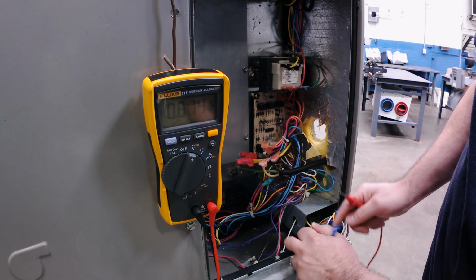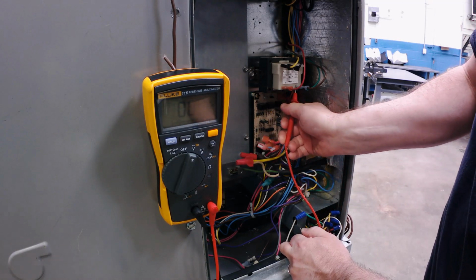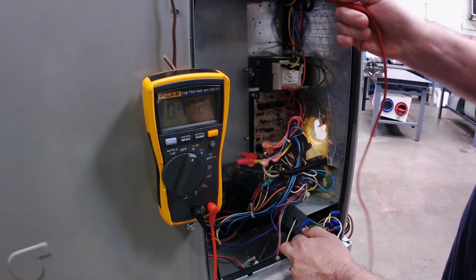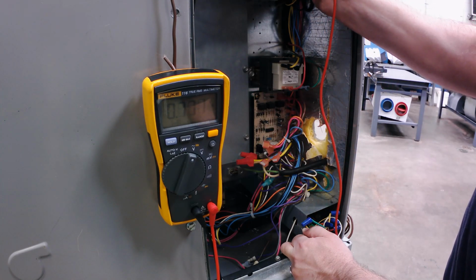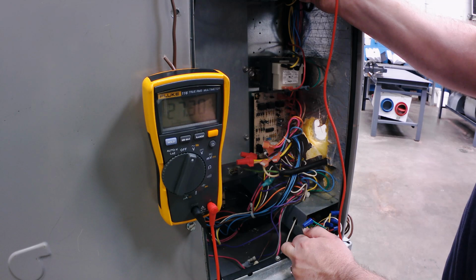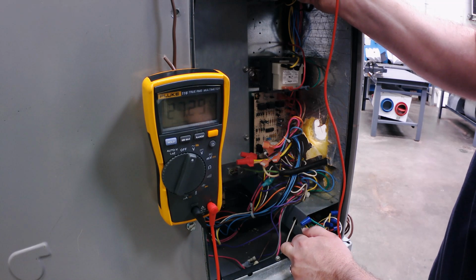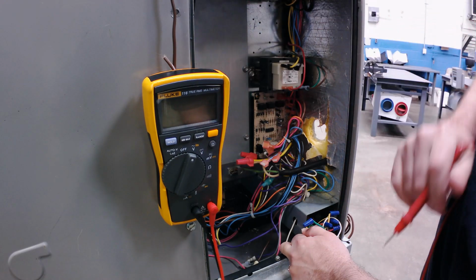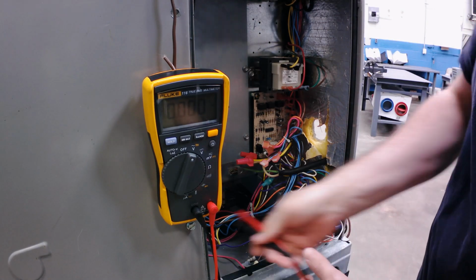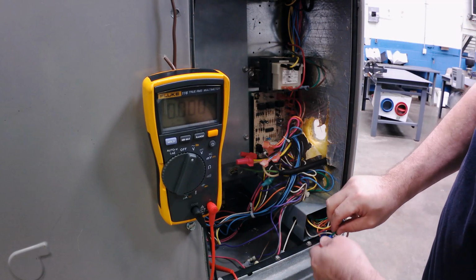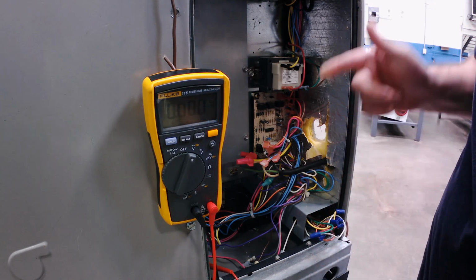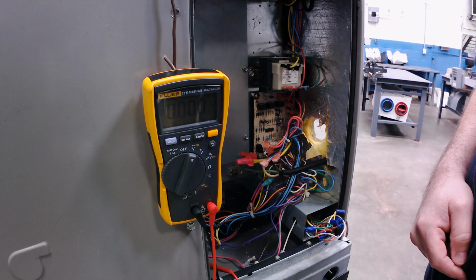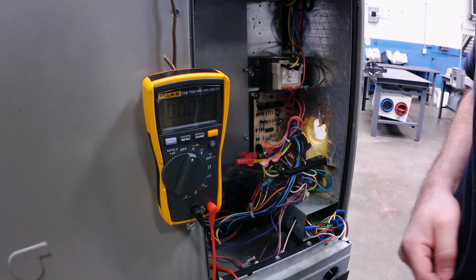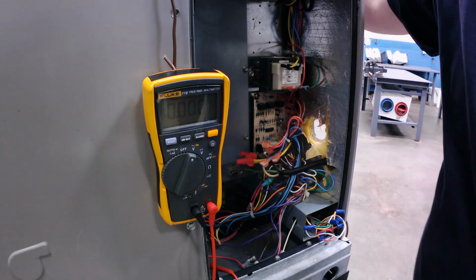Okay, so check the common on the transformer. Even if you grab the common in this package unit, I could grab the common off of the contactor coil, because common is common is common. As long as you know it's a common, you're on the correct side of power there. So if you didn't have 24 volts, that's when you would check something else. Okay, so in my case here, let me.